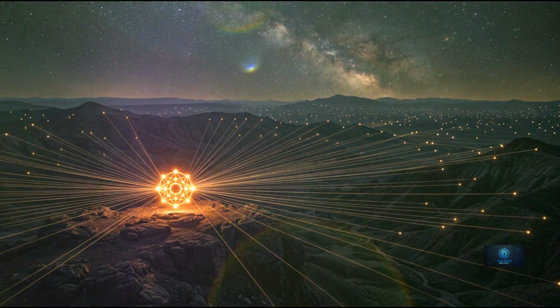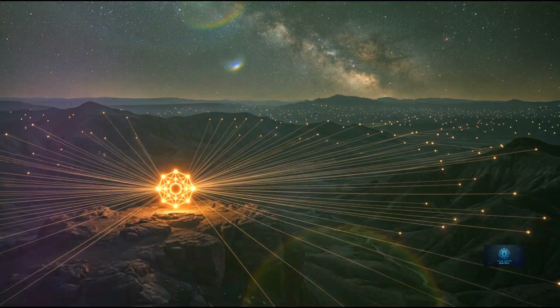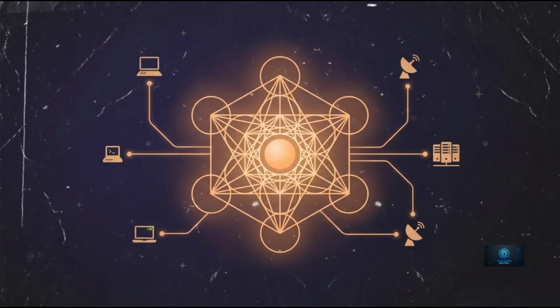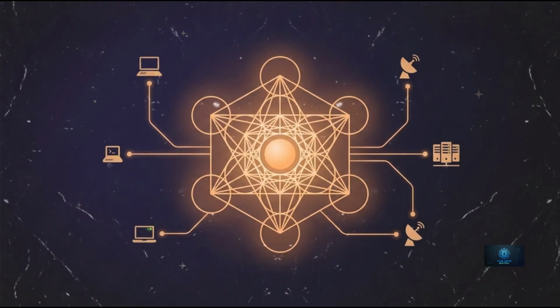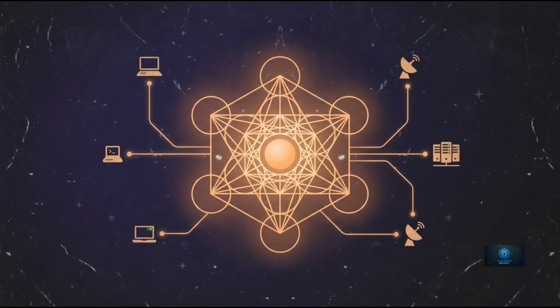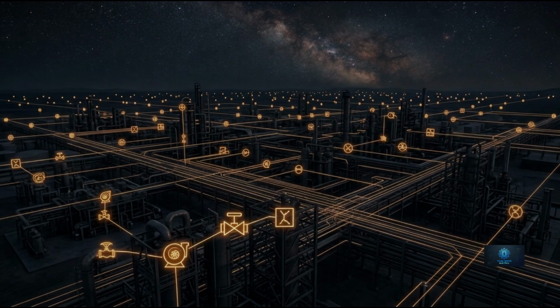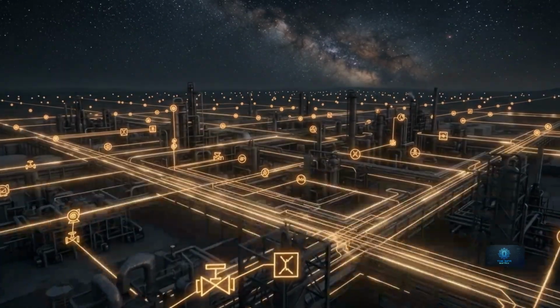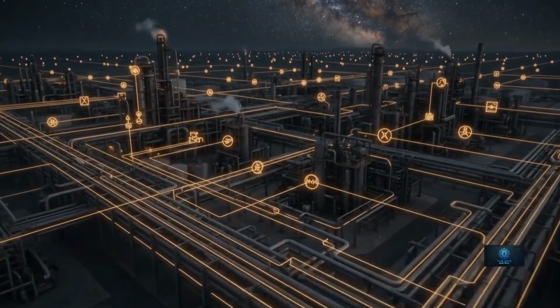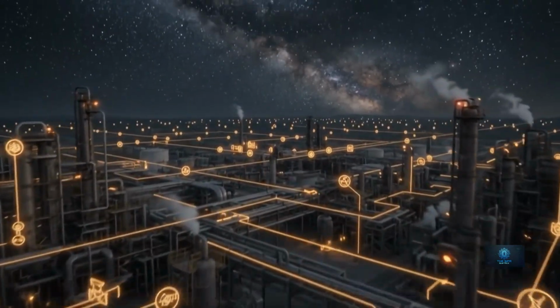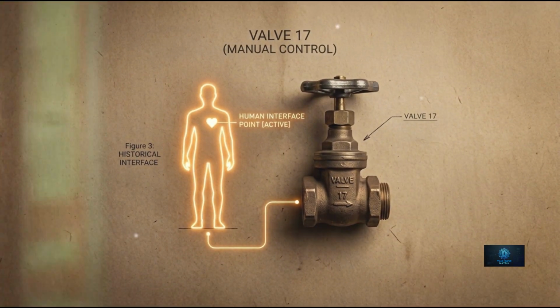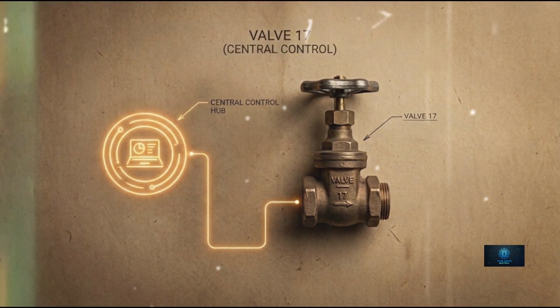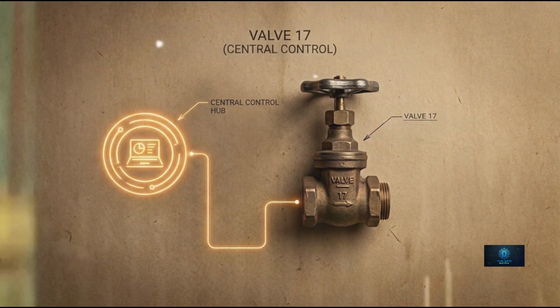SCADA stands for Supervisory Control and Data Acquisition. It's not one piece of equipment, it's an entire system designed to do two things: acquire data from equipment spread across a wide area, and let operators supervise and control that equipment remotely. Think of it as the nervous system connecting a control room to hundreds, sometimes thousands, of physical devices scattered across a facility, a city, or a region. Without SCADA, every valve, pump, and breaker would need someone standing next to it, watching it manually. With it, one team can oversee it all from a single room.